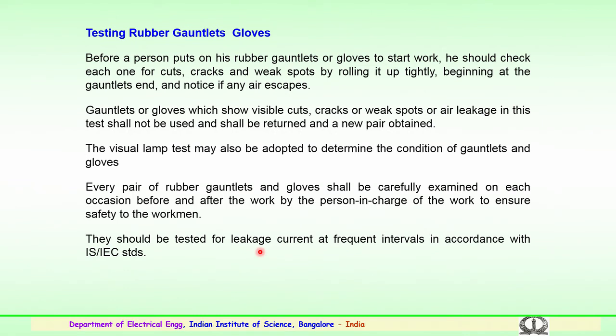At regular periods, before the person uses the rubber gloves or gauntlets, it is his duty to check each one for cuts, cracks or weak spots by rolling it tightly, beginning at the gauntlets, and also to notice if any air escapes, that is, to verify if there is a leak in the gloves or gauntlets. If they show visible cuts or cracks, they should not be used, and they should be returned and a new pair obtained and used for the job.